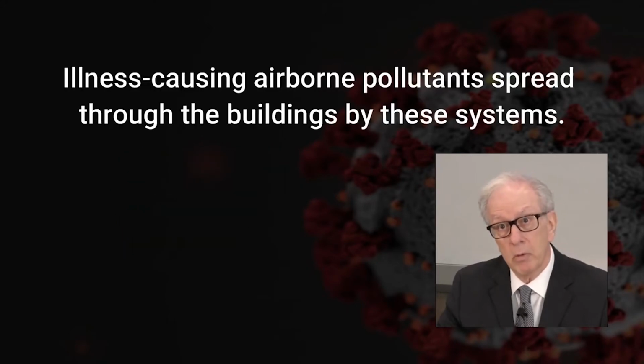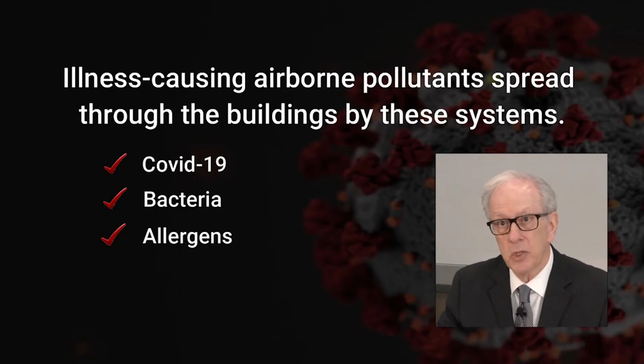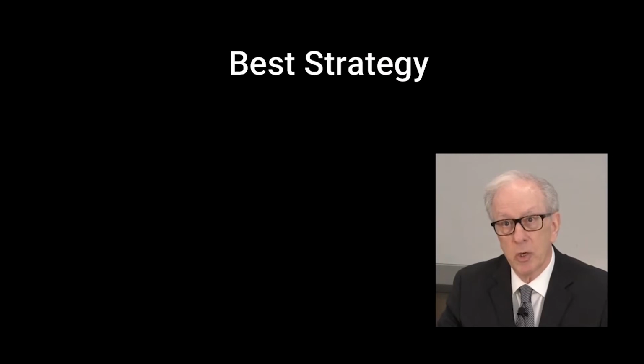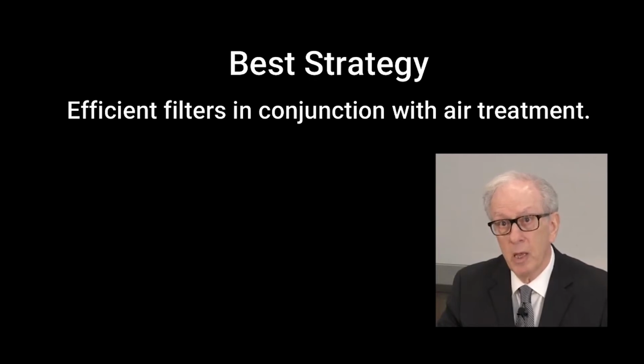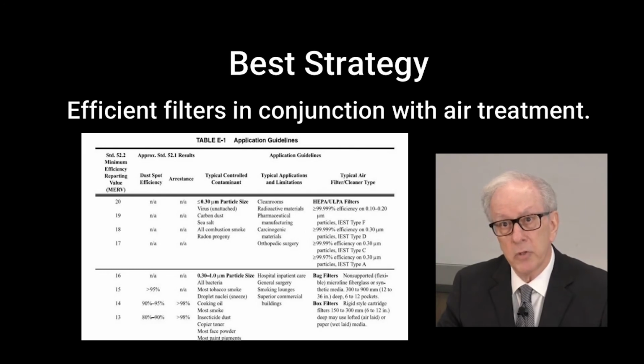Illness-causing airborne pollutants spread through the building by these systems include COVID-19, all other viruses, bacteria, allergens, and cancer-causing VOCs. The best strategy for ridding the airstream of these pollutants is to provide efficient air filtration in conjunction with pollutant-destroying air treatment. MERV 13 or higher air filters inside of air handling units will effectively remove particles as small as 0.3 microns in diameter. Smaller pollutants, including COVID-19, that pass through the filters need to be combated by other means.